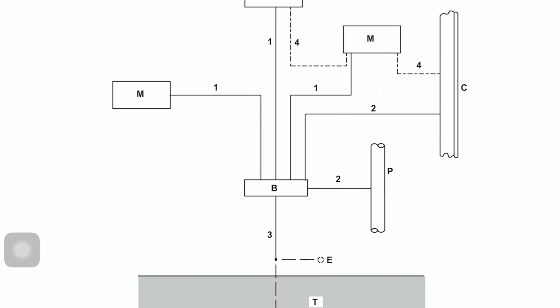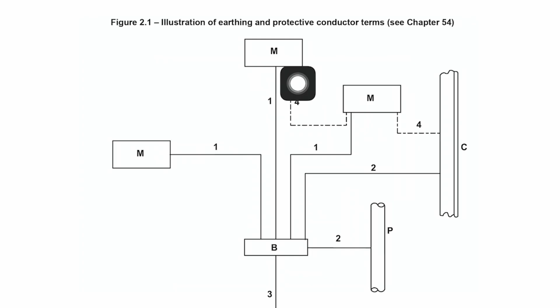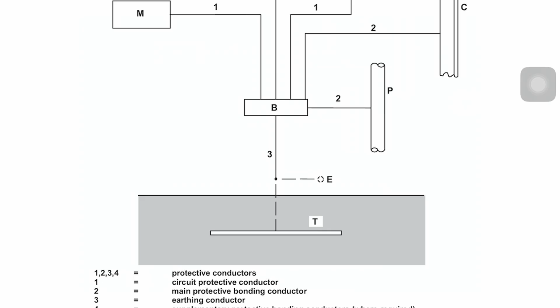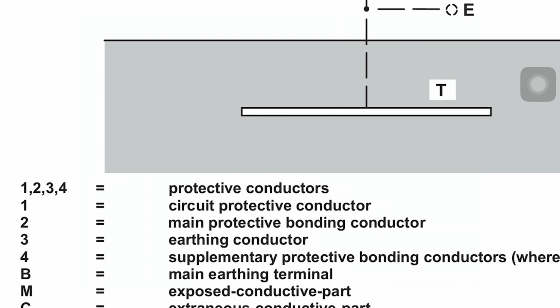And over here we've got a steel stanchion. And this is a pipe coming out of the ground. So look, number 2. There are different types of conductors here, and they are main protective bonding conductors. And the ones with the dotted lines are supplementary protective equipotential bonding conductors. The one that catches everyone out is number 3, so I want you to pay attention to that. This is the conductor that connects the main earthing terminal to the means of earthing, and you can see down here that it's just 2 words, and it's called an earthing conductor.